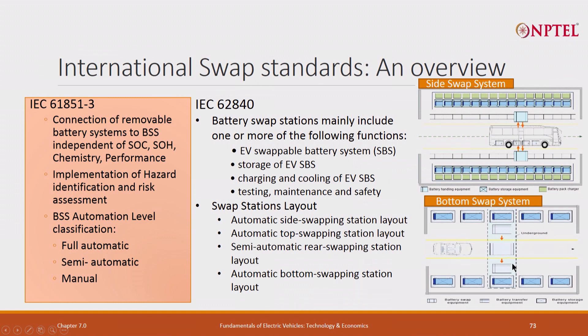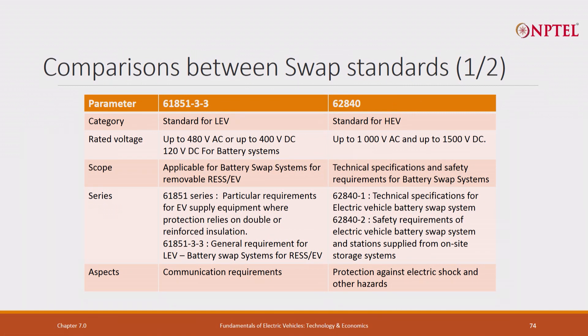The battery swap station mainly includes an electric vehicle battery swap system, storage for EVs, SBS, charging and cooling, and testing and maintenance. There is some attempt to standardize swap station layout — not really standardize, more as a guideline. The vehicle comes in, you swap, and the vehicle moves out. The two standards — 61851-3-3 and 62840 — one is for LEV low-end vehicles and one is for very high-end vehicles, with 1000 V AC and 1500 V DC; the LEV standard covers up to 480 V AC and 400 V DC.